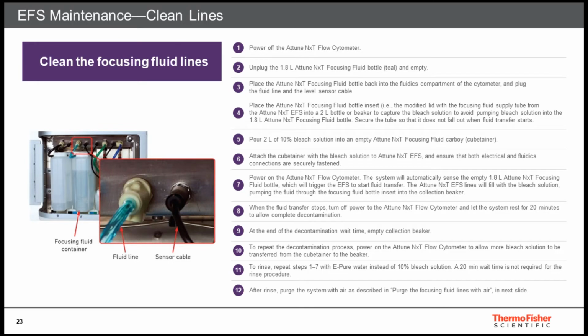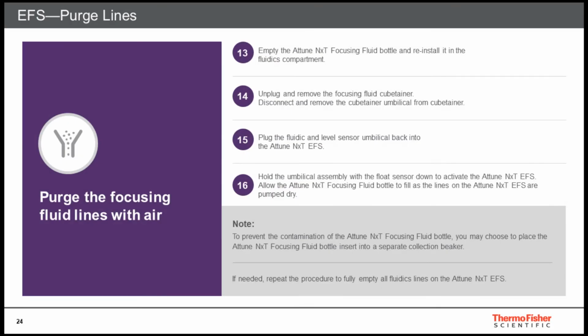If an external fluid supply is present, please go through the cleaning procedure described in the maintenance guide or the steps listed above. In summary, the steps are similar to the decontamination script, where 10% bleach is run through the lines in the EFS system, then rinsed with DI water and refilled with appropriate fluids. An empty focusing fluid cube is required, so save an old container that can be rinsed clean for the purposes of EFS maintenance. For the purpose of storage, the EFS system can be purged with air and left in a non-operation state for a prolonged period, or fitted with a new focusing fluid cube container for immediate use.